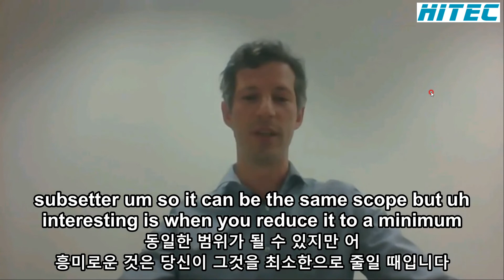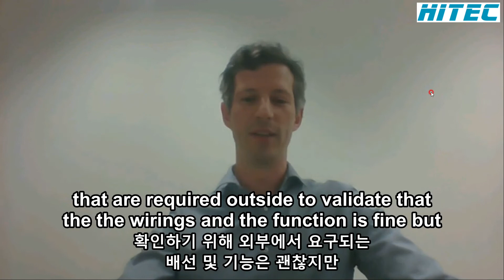Okay, thank you for that. And you can also select what tests have to be performed on site. So it can be the same scope, or interesting is when you reduce it to a minimum—not testing all the protection characteristic information, but only the interesting operating points required at site to validate the wiring and the function, without going into the details that are just part of a virtual test or factory acceptance test.